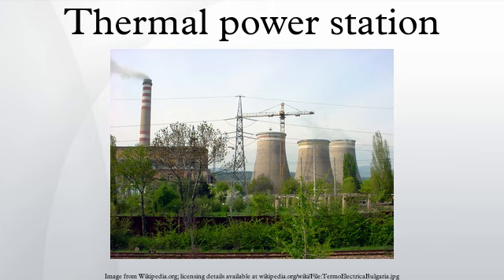The limiting factor is the temperature of the cooling water and that, in turn, is limited by the prevailing average climatic conditions at the power plant's location. Plants operating in hot climates may have to reduce outputs if their source of condenser cooling water becomes warmer. Unfortunately, this usually coincides with periods of high electrical demand for air conditioning. The condenser generally uses either circulating cooling water from a cooling tower to reject waste heat to the atmosphere, or once-through water from a river, lake or ocean.